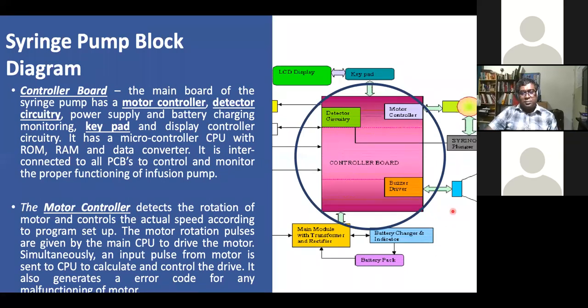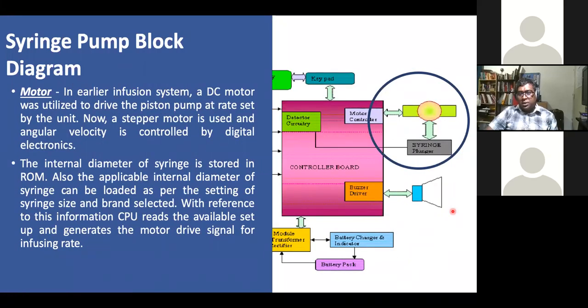You see the motor circuit? They use a DC stepper motor that takes a step signal and moves that particular line, and the movement is all monitored. The motor is attached to the mechanism and it moves accordingly. For a syringe pump, normally the syringe is about 60 ml or below. So when you set 50 ml, the information is sent and the motor is going to follow according to the rate, movement, and velocity, all that. So you can monitor the particular information, how many milliliters have been delivered, all that, on the display.